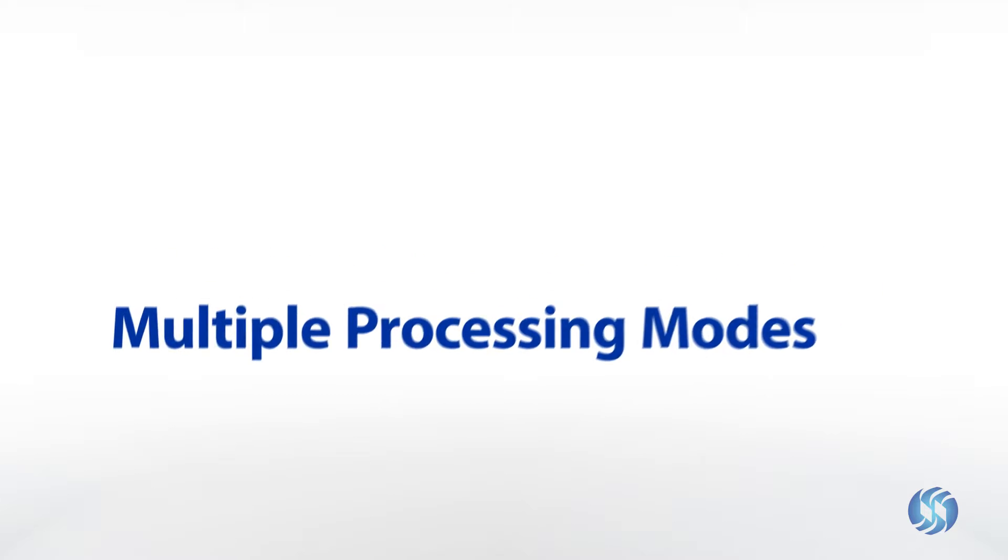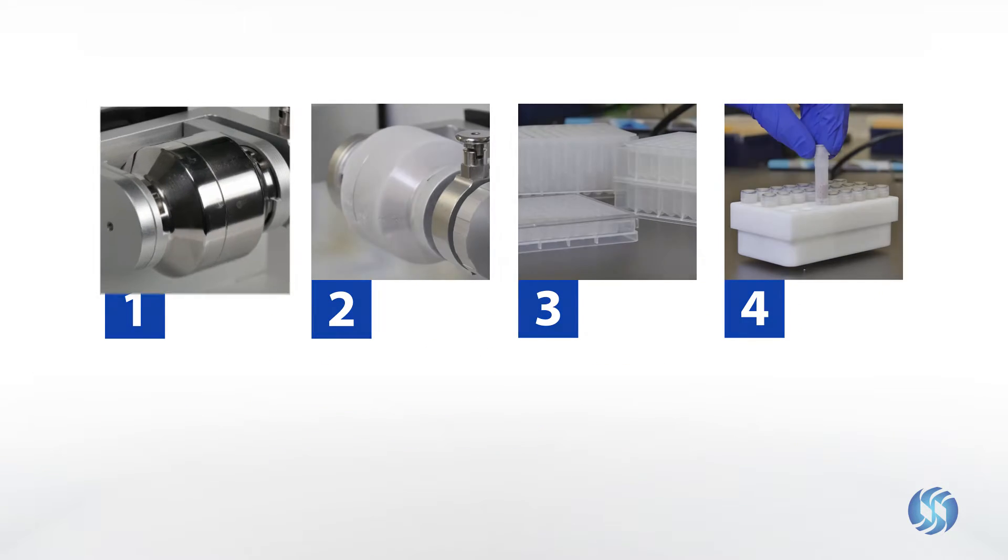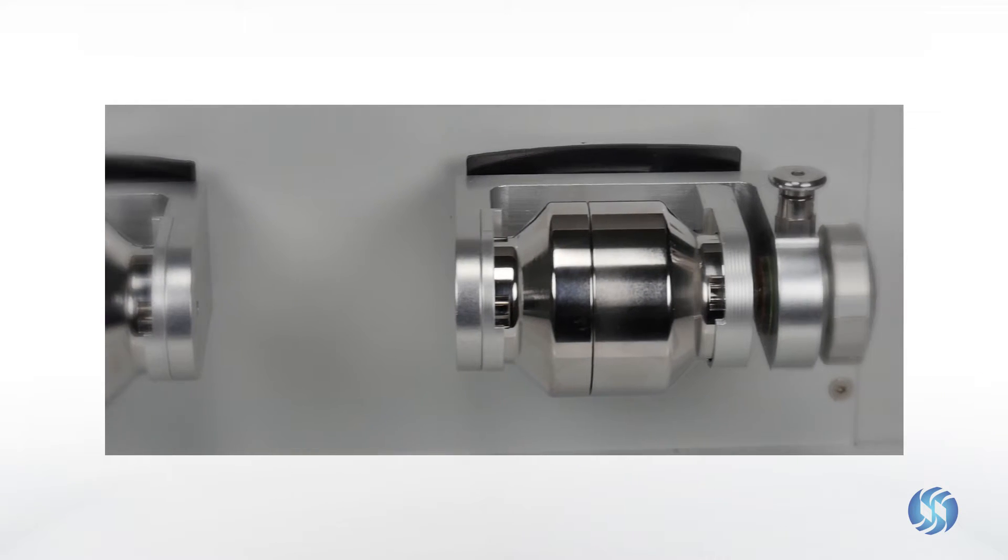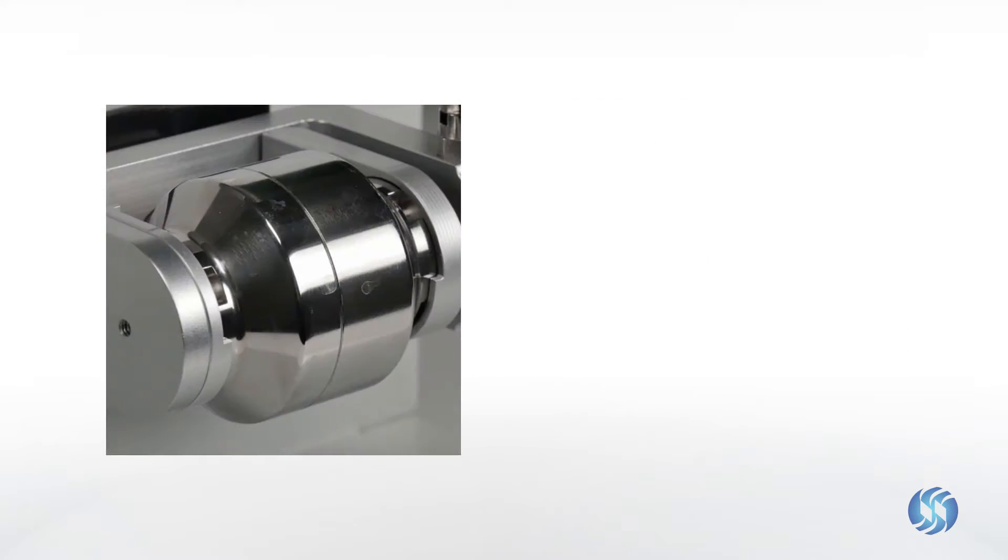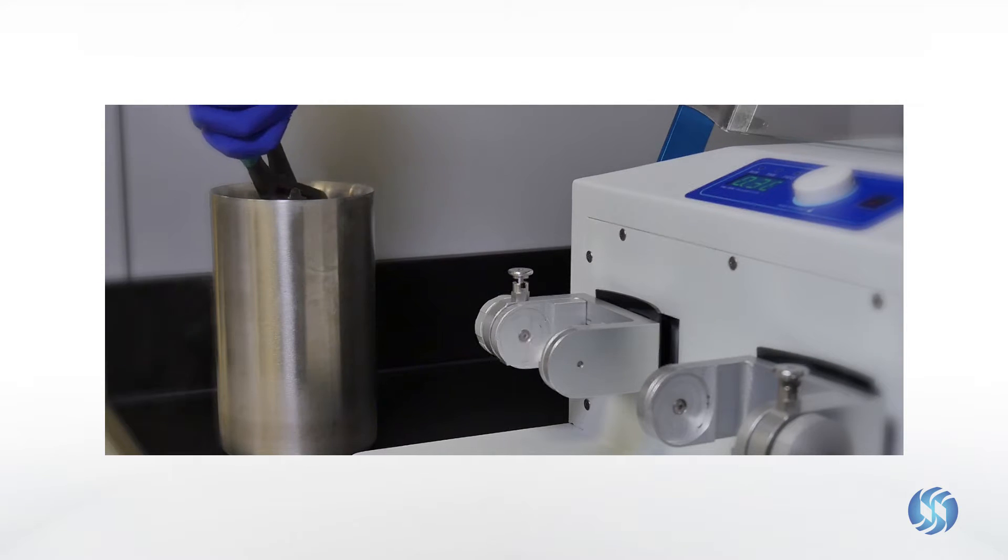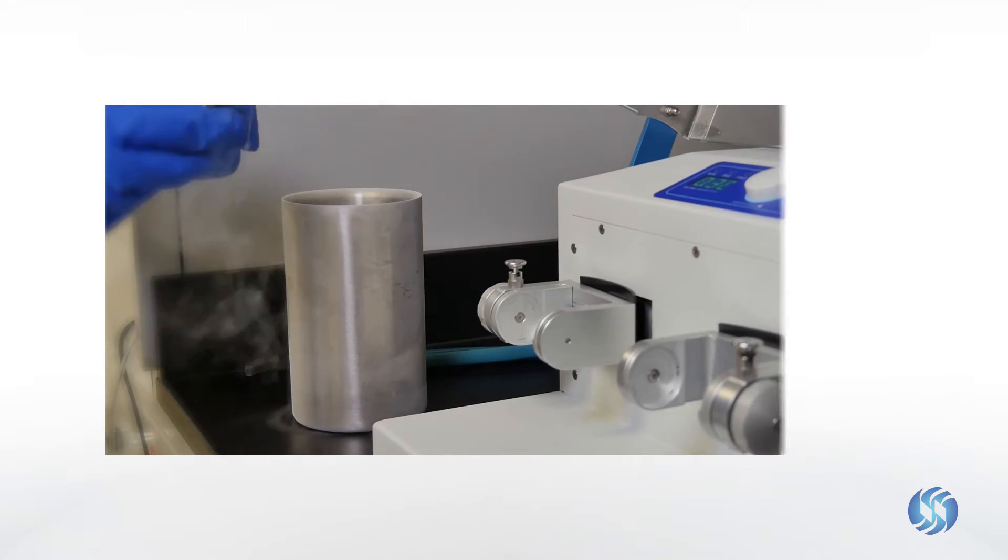The Beadruptor 96 enables multiple processing modes ensuring utility for a broad range of applications and sample types including stainless steel jar processing in volumes up to 50 milliliters for dry or wet milling applications. Tough materials including plastics, bone, and minerals can be ground under cryogenic conditions by cooling the stainless steel jars in liquid nitrogen.